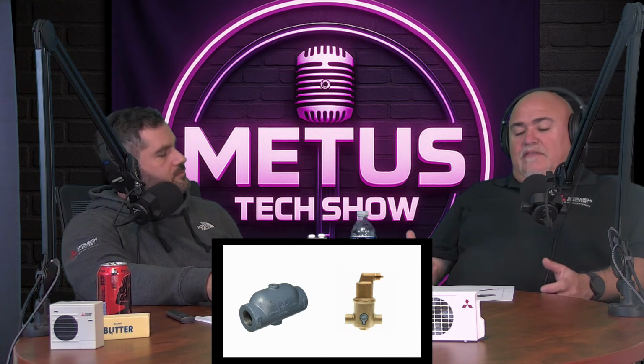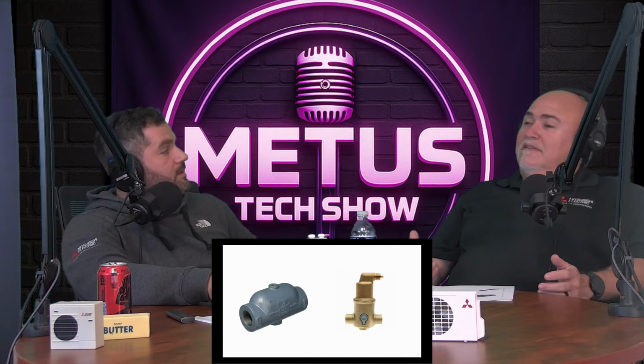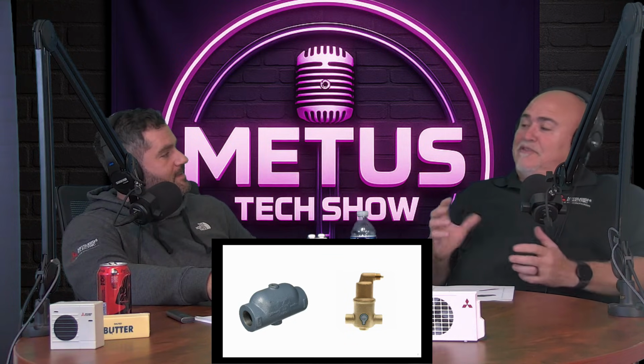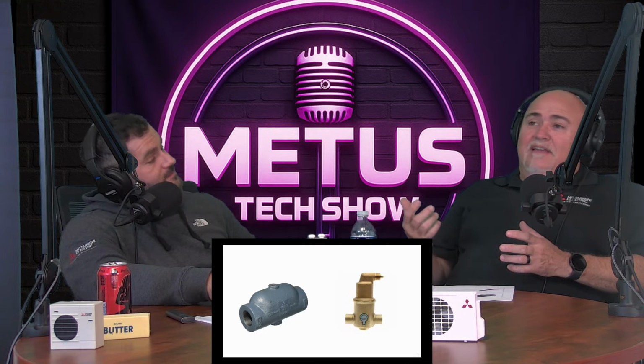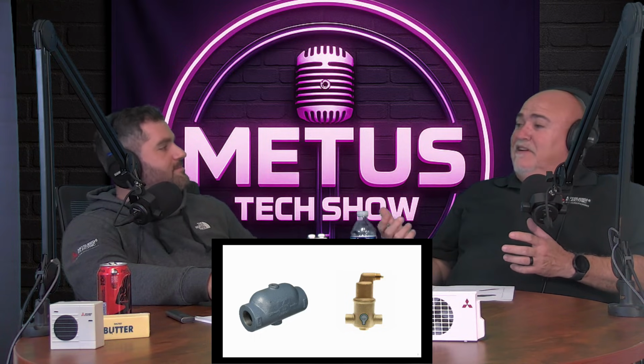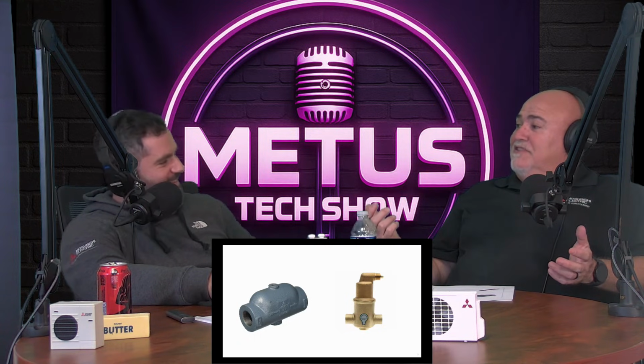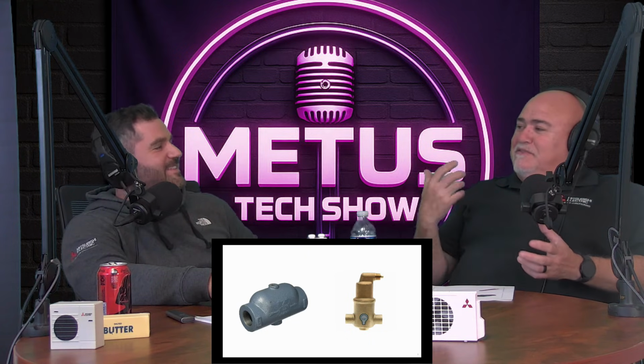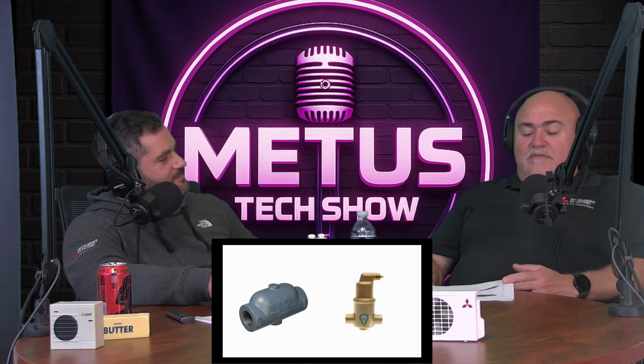When you had the cast iron air scoop, we would just screw the expansion tank into the bottom of that. But the expansion tank would fail. Now you'd have to drain the whole boiler just to change it. Now they put a ball valve in there. We've gotten a lot smarter with that stuff. Yeah.